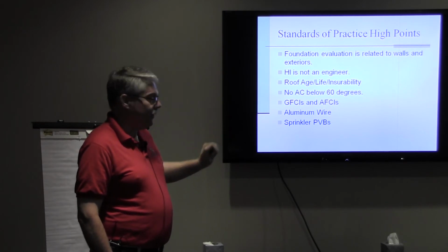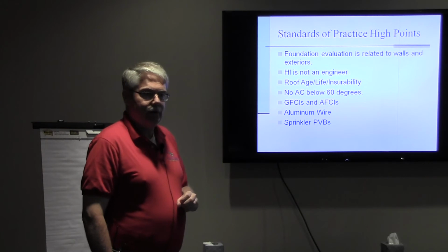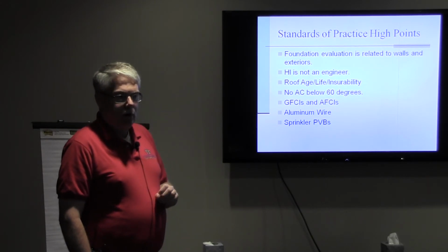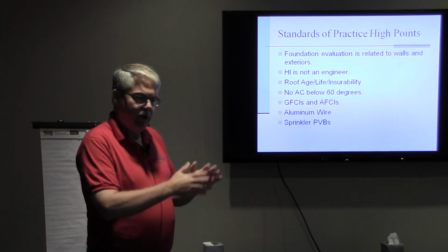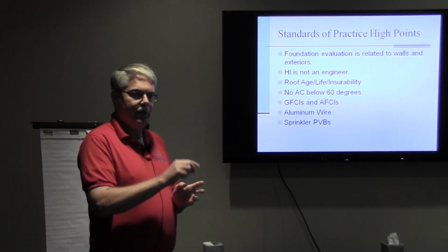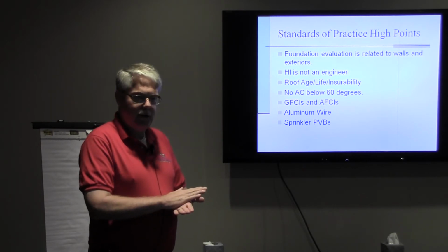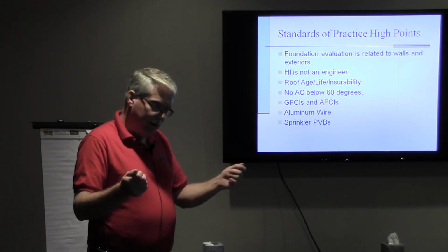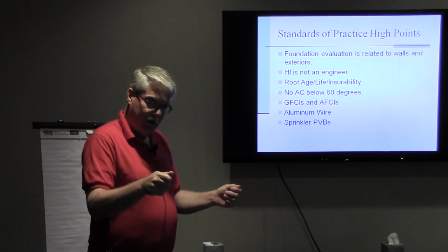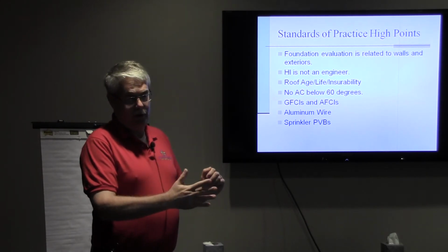Now, arc fault circuit interrupters, AFCIs, are new. They weren't required in code till 2004. What an arc fault circuit interrupter is, to separate it from a ground fault circuit interrupter, GFCI is installed in outlets, and it protects you when electricity gets in contact with water and grounds out, because if you're the one touching the plug and something in the sink, it only takes a 1/4 amp to stop your heart.